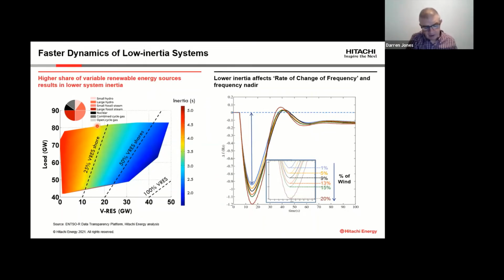What we have on the left is some analysis that we did at Hitachi Energy with some of our colleagues in Europe, an engineering technical research organisation. We've done quite a bit of research with them, looking at the implications of ever increasing penetration of renewable energy as a proportion of the load being served. It follows completely from the previous description of those equations: the more renewable energy we have, the less inertia we have, the lower the inertia constant. As the inertia constant reduces and the system becomes more unstable, with the faster dynamics of these low inertia systems, we may need to use other means and methods to try and control the system.